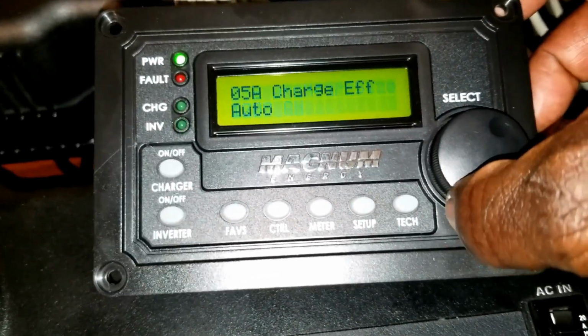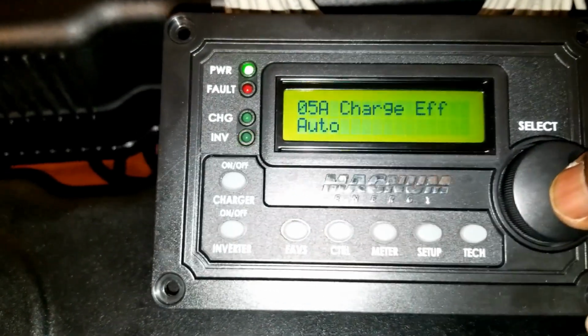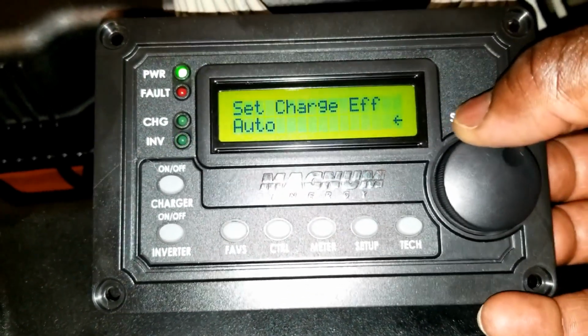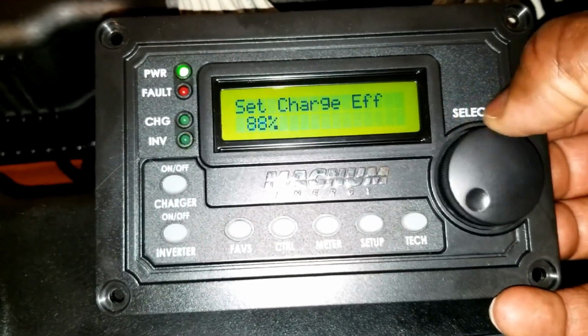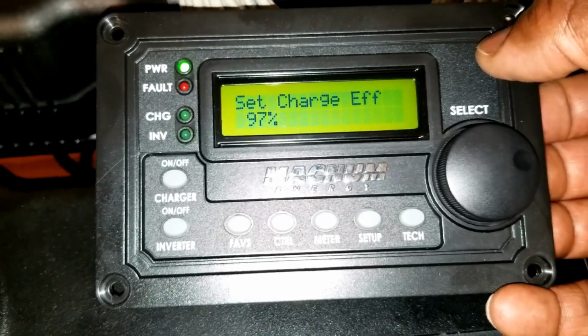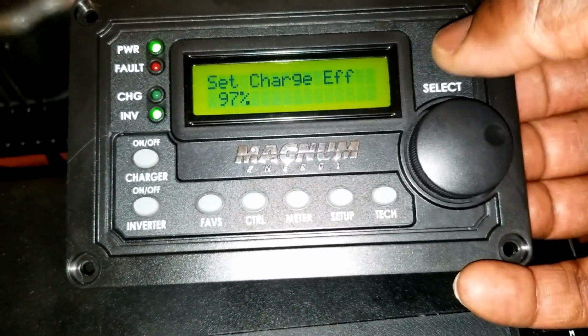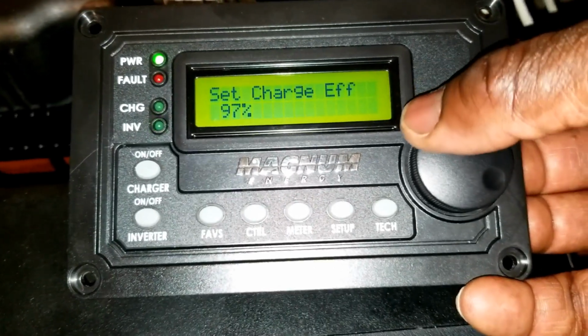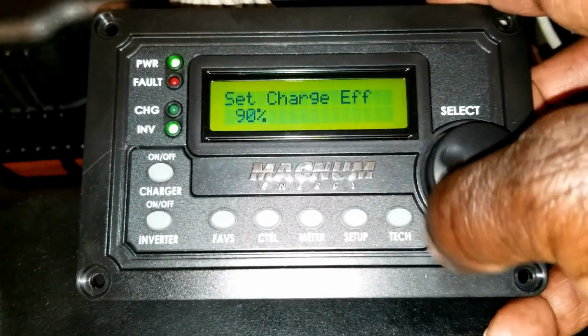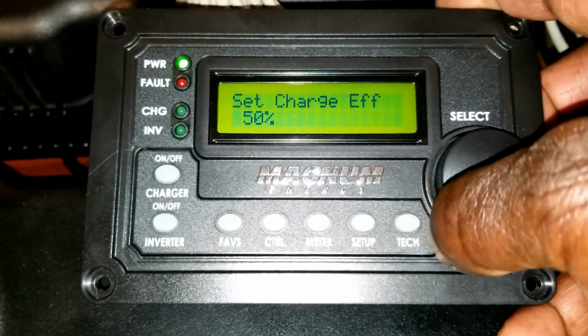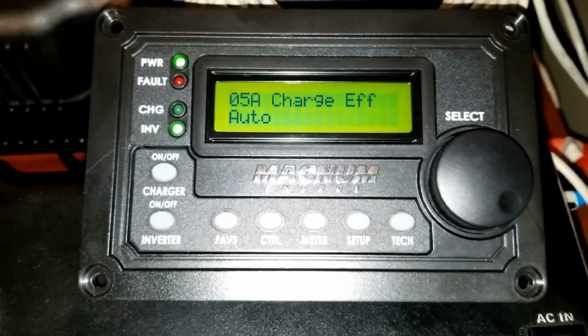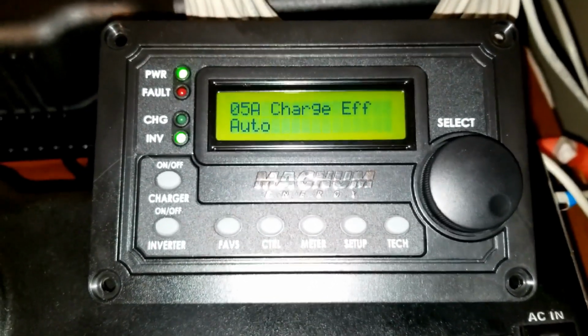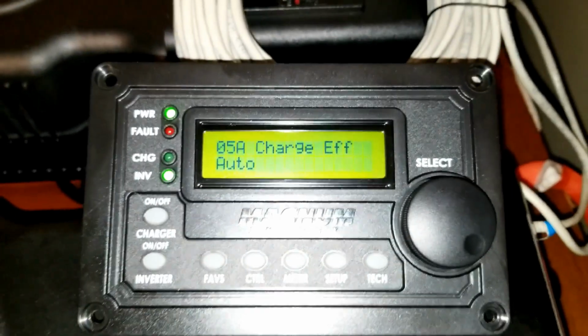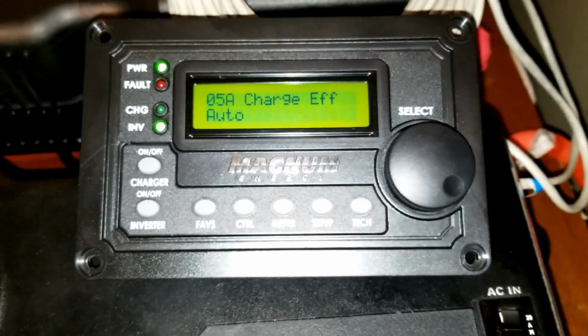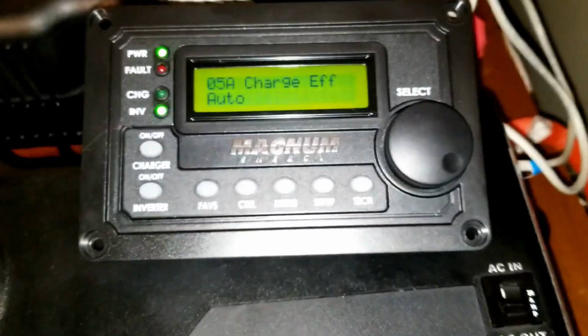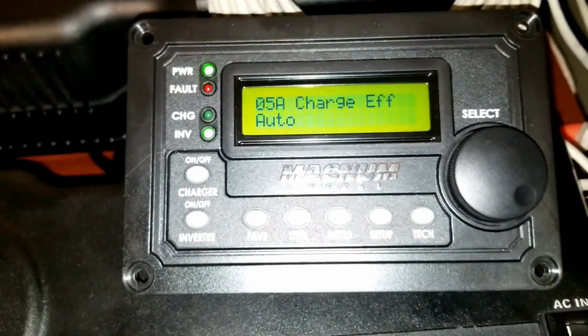So we're done with that, we leave it on auto. If you want to tweak the thing, do the efficiency. Some people like to set it if you know the battery manufacturer's efficiency, and you can just set it to 97, the highest efficiency. Or you can dial it back to 50, the auto, go auto right away. So we'll keep it on auto, so the machine will determine the efficiency of the battery, how effective they are, or how much power they can handle. Since these are not brand new modules, they're used already, so they already have some degradation on them.